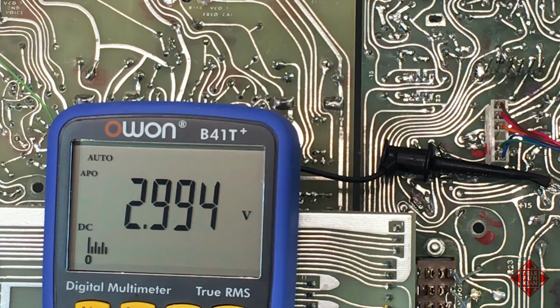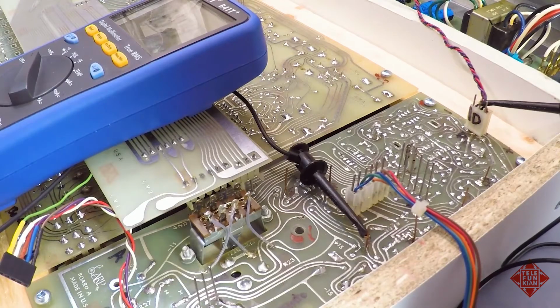Now we do see a modest decrease in voltage, which may need to be addressed. But regardless, we see it very close to that 3 volt level. We're looking for no more than a 20 millivolt change in that voltage over the course of 1 minute. And although it has decreased by 6 millivolts, I would suggest that that's probably performing as it should. The second test at test point 3 is to depress and release high C.